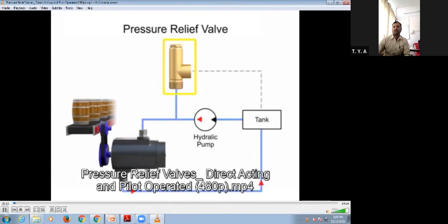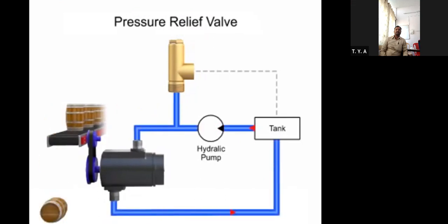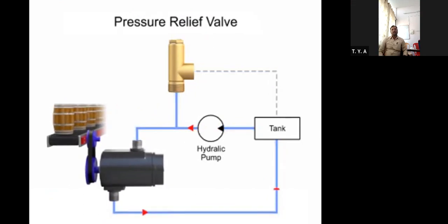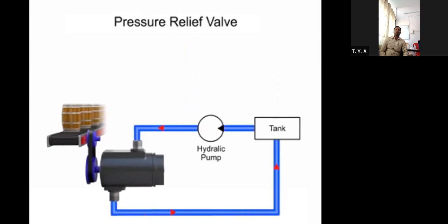Pressure relief valve is one of the most important types of safety valves. This type of valve sets a limit on the rise of pressure within a hydraulic line. In normal operations, the valve is closed and no fluid passes through. But if the pressure in the line exceeds the limit, the valve opens to relieve the pressure. This protects expensive machinery such as motors, pumps, and actuators from becoming damaged from high pressure. Without a relief valve, pressure can continue to grow until another component fails and pressure is released.